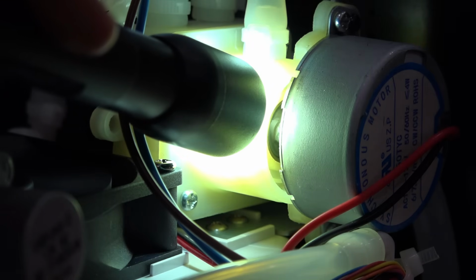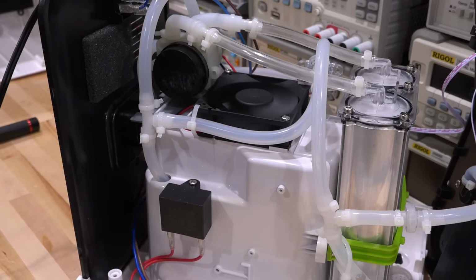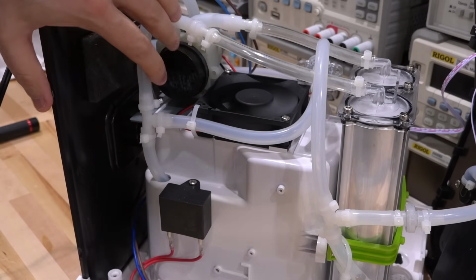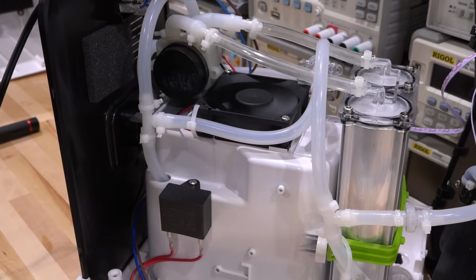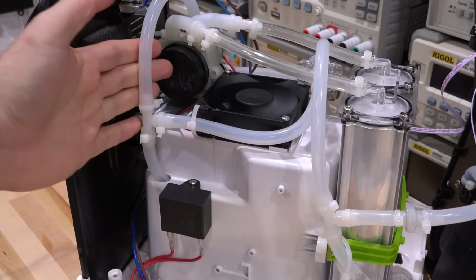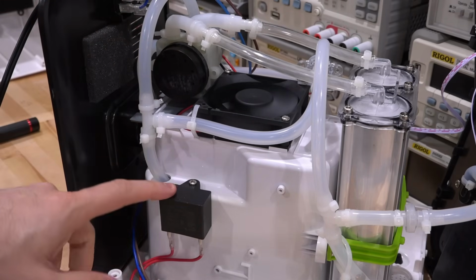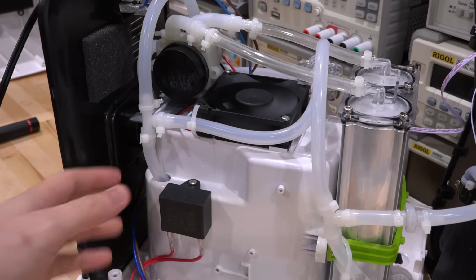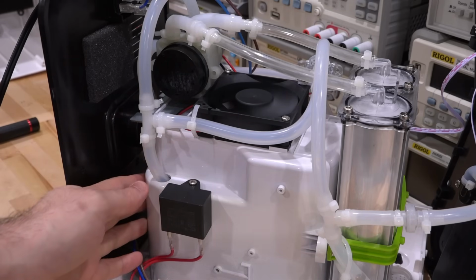Yeah, quite simple. And on the other side of the unit, we see a few other things. This is the main exhaust. This is where the nitrogen-rich gas comes out. So in theory, you could actually connect something in here and have some perhaps higher purity nitrogen coming from here as well. And this is the little capacitor for the compressor inside. The compressor is nothing really fancy. It's just a really basic compressor there.